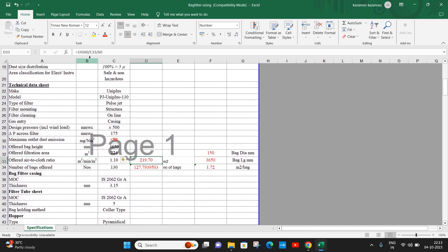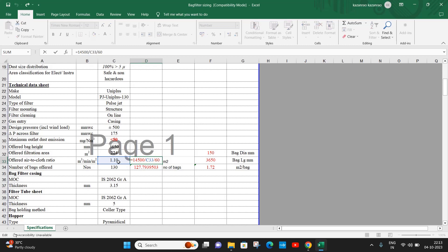Convert it to meter cube per minute and divide by 1.1. So 14,500 divided by 1.1, divided by 60. The gas volume divided by air to cloth ratio, divided by 60.